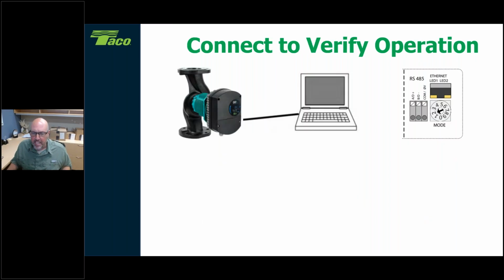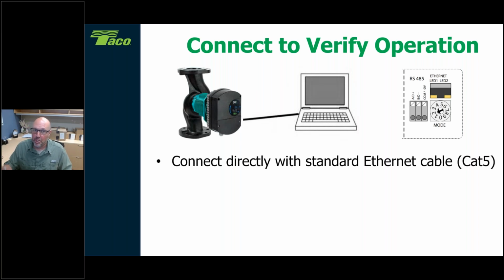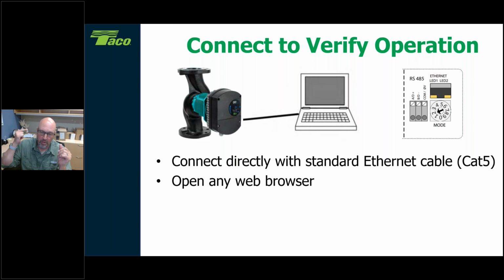Now, here's the fun stuff that you got outside of the faceplate programming, right? We do those faceplate programming and you want to do a little bit more, all right? Now you could take your laptop, tie it into the circulator itself, and get a little bit more details and a few more operations that you can't get from the faceplate. What we're going to do is tie in with a standard Cat5 cable. So you got that port on the back side under the electrical box in here, tie it directly into a computer. There is no app, there is no special software that you need to download. It is just using your standard web browser.